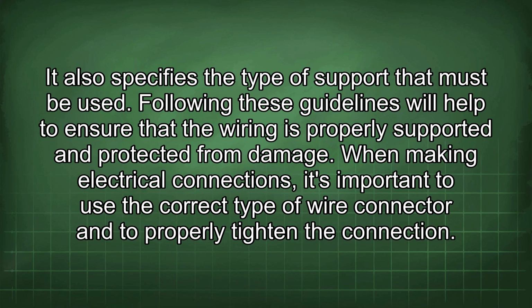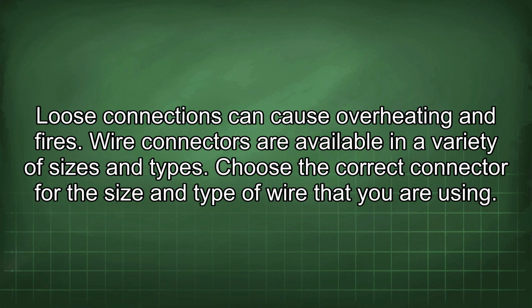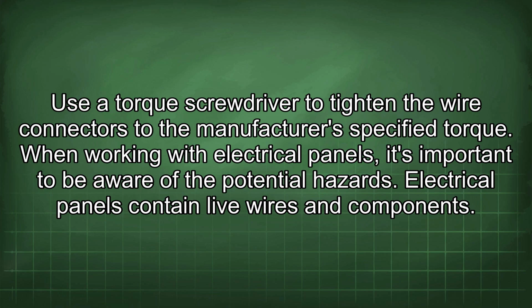When making electrical connections, it's important to use the correct type of wire connector and to properly tighten the connection. Loose connections can cause overheating and fires. Wire connectors are available in a variety of sizes and types. Choose the correct connector for the size and type of wire that you are using. Use a torque screwdriver to tighten the wire connectors to the manufacturer's specified torque.